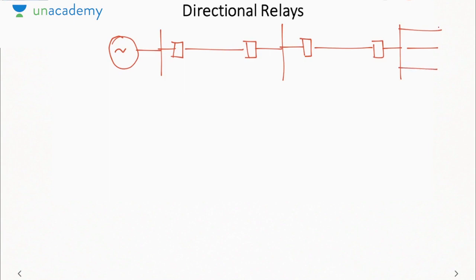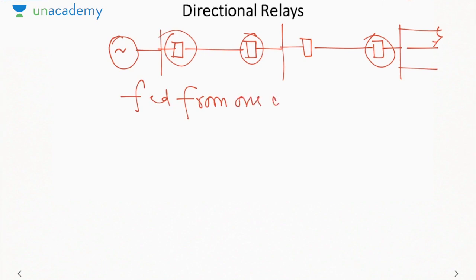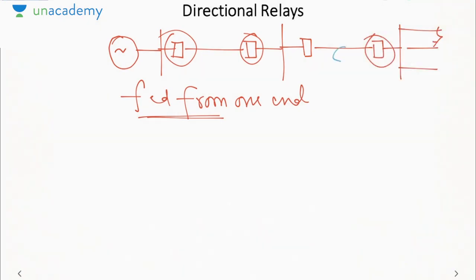Suppose like this. Now if a fault was occurring here, it was understood that this will operate first, then this, and the last one should be this. But now this system was fed from one end. So there was no problem of the conflict of the relay operation, because suppose the fault was occurring here.